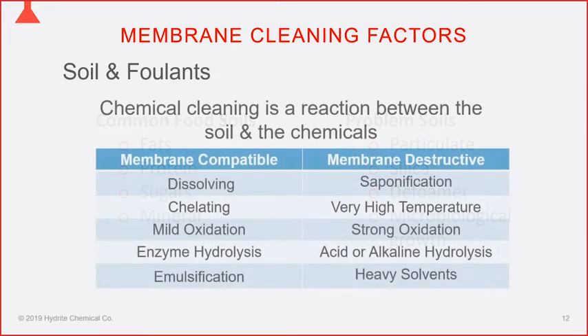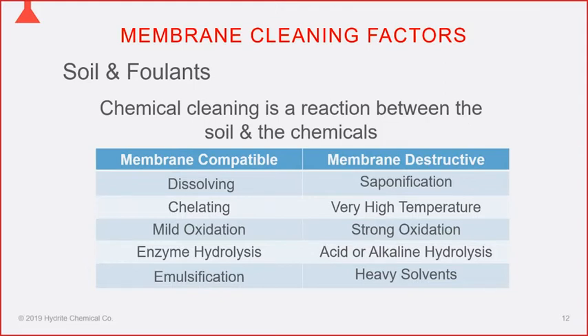It's very important to monitor CIP logs to make sure customers are sanitizing their membranes on a regular basis. The most common soil removal mechanism is dissolving — like granular sugar dissolving in hot water. Not all soils readily dissolve, so we sometimes use chelating agents that dissolve mineral soils not soluble at pH 2. We can also oxidize soils through hypochlorite or peroxide — breaking proteins into amino acids. For membranes that can't tolerate oxidizers, enzyme hydrolysis can break proteins into amino acids.